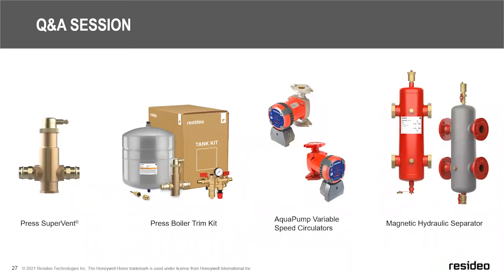So these can have constant power. It'll see the zone valves or manifold actuators open and close and adapt the flow as it needs. It's actually kind of cool. I'm a bit of a nerd. It's kind of neat to sit there in the mechanical room and manually open valves and watch the display on the circulator flash between flow rate and wattage consumption. It's a pretty neat little thing to see. So there are a lot of people that just plug these in and essentially run them 24/7. When it's sitting idle, it's only drawing like 5 or 6 watts. So there's hardly any electrical consumption when they're sitting idle with no flow.